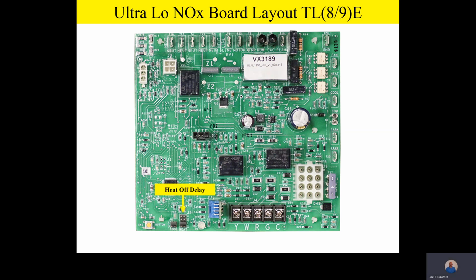Another feature on the board is a heating off delay. We see we have an ABCD function on the heating off delay. What this field selectable jumper does, it allows the technician to set up our heating off delay. In other words, once the call for heat goes away and the thermostat is satisfied, the fan continues to run to distribute that residual heat on the heat exchanger into the conditioned space. And there's 4 selections, A, B, C, and D.